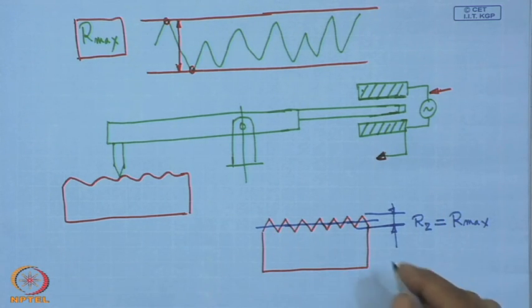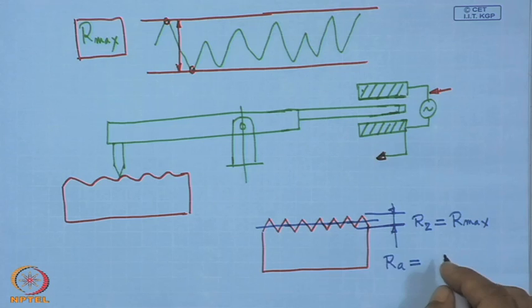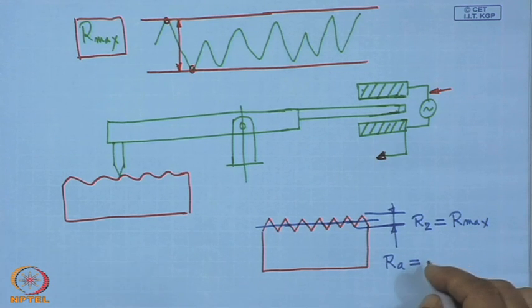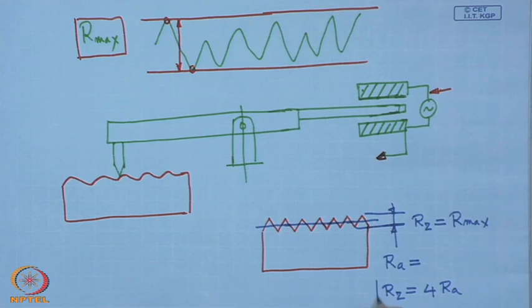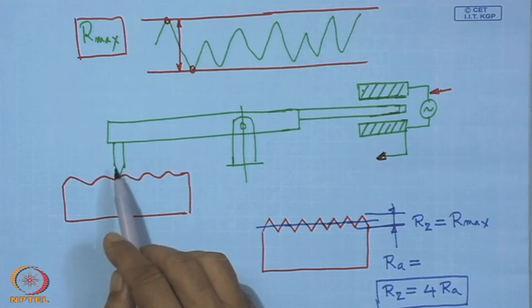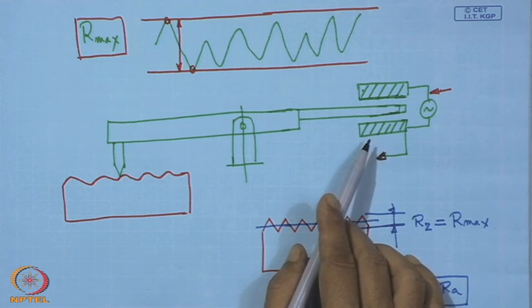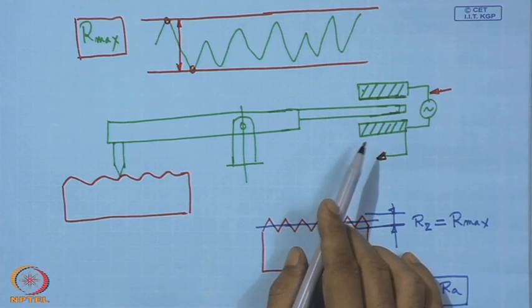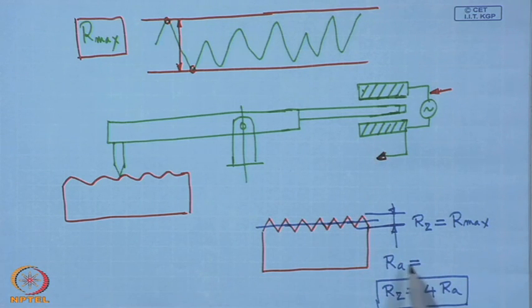In this case, the R a value is given for this master gauge or masterpiece, and R z is equal to about 4 times R a, geometrically. These values are given, and accordingly this instrument's amplification factor or sensitivity factor can be adjusted according to this already given value. So this instrument is ready and can be used for routine measurement of surface roughness.